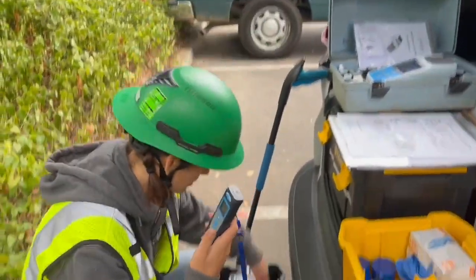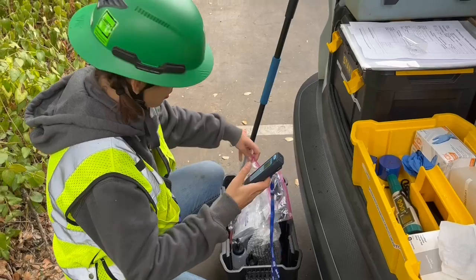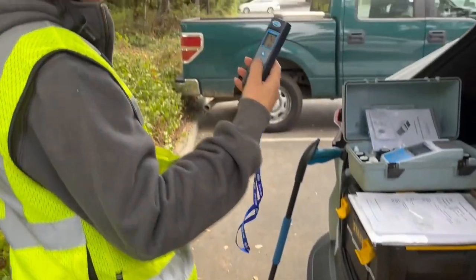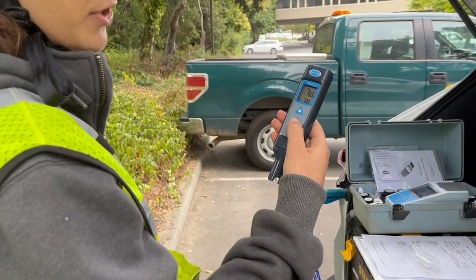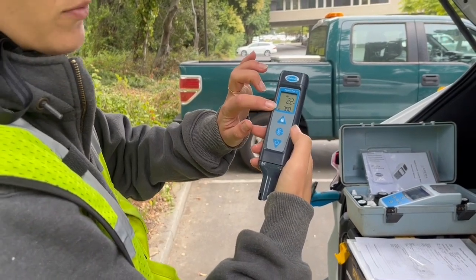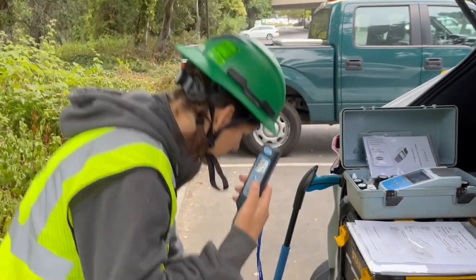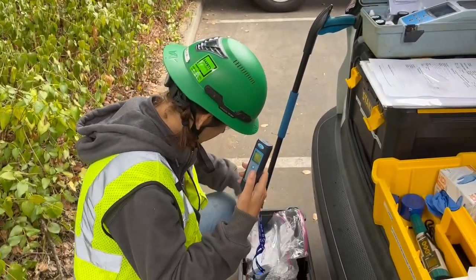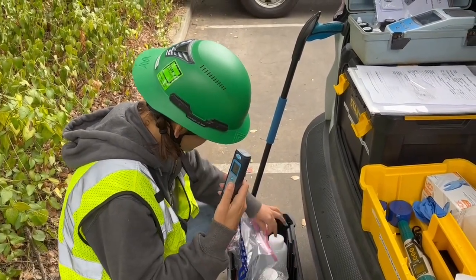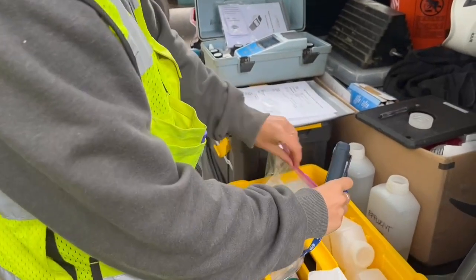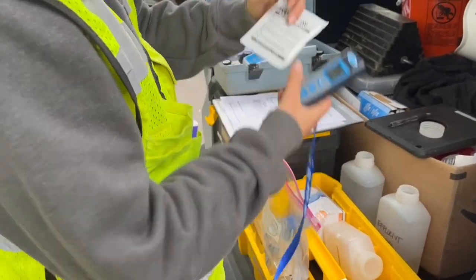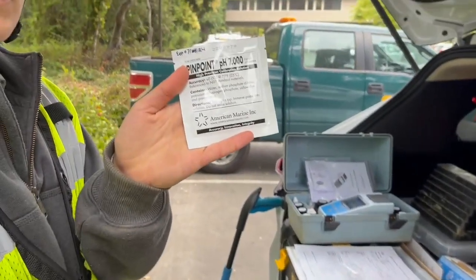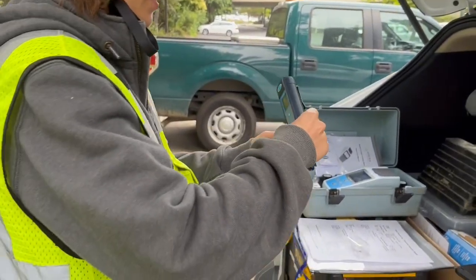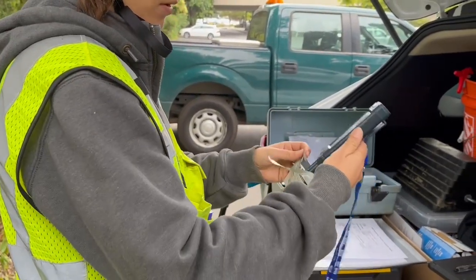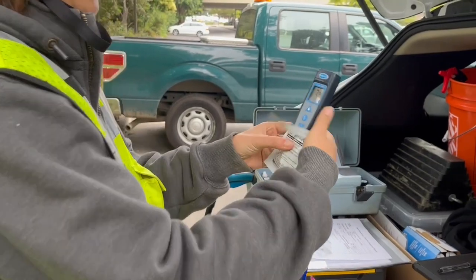So we have multiple different calibration solutions here. First thing I want to do is select 3-point calibration. It's prompting me to use the 7.0 packet. So right here, I've got a packet that says 7.0. What I'm going to do is tear it open, put the probe in the packet.